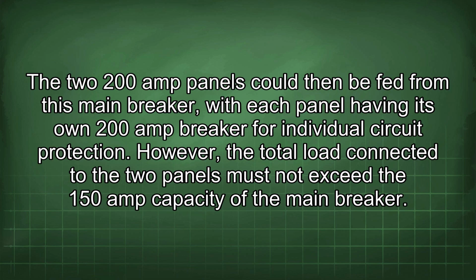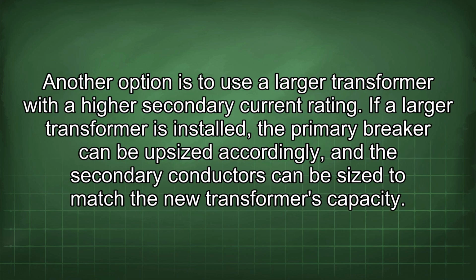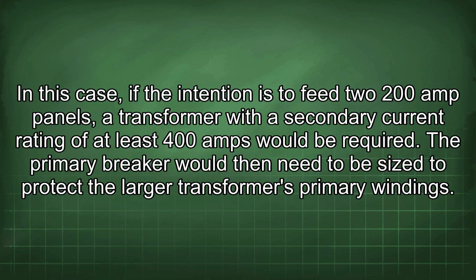the main breaker. Another option is to use a larger transformer with a higher secondary current rating. If a larger transformer is installed, the primary breaker can be upsized accordingly, and the secondary conductors can be sized to match the new transformer's capacity. In this case, if the intention is to feed two 200-amp panels, a transformer with a secondary current rating of at least 400 amps would be required. The primary breaker would then need to be sized to protect the larger transformer's primary windings.